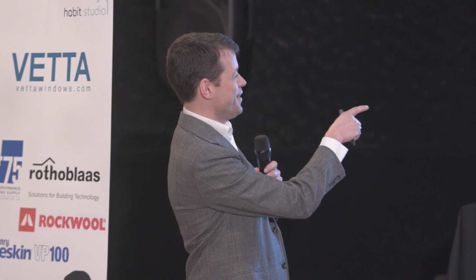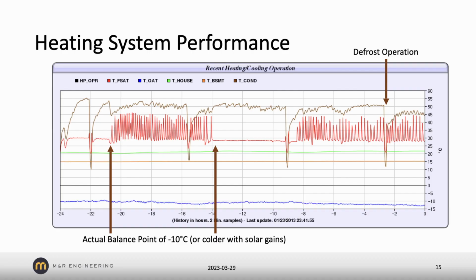A little bit on performance here. All I want to point out here is the red line again. The red line is my supply air temperature from the heat pump. It's about 30 degrees Celsius. But you can see that it starts getting really jagged at one point in time. Whenever it gets a little bit colder outside, that means the supplemental heat is starting to kick in. If you look at the blue line across the bottom, it's just below -10 or right around -10. That's the outside air temperature.